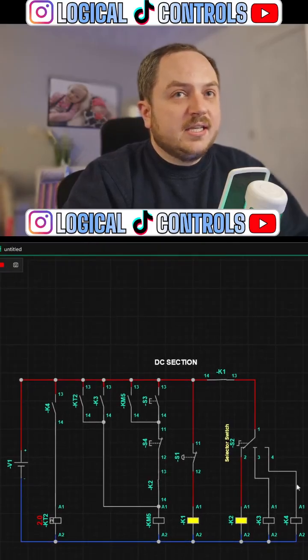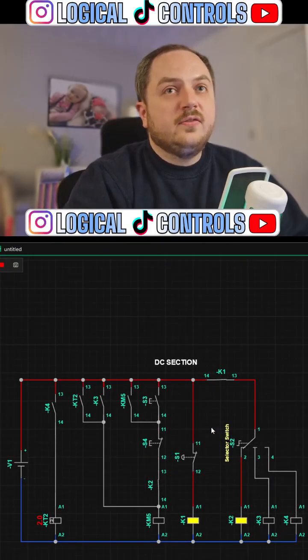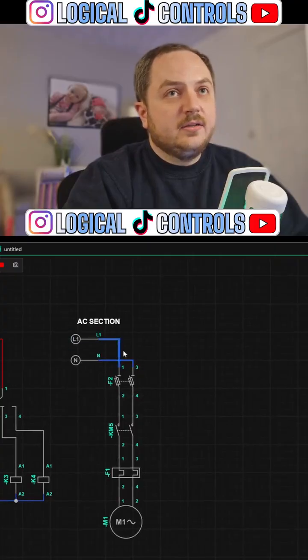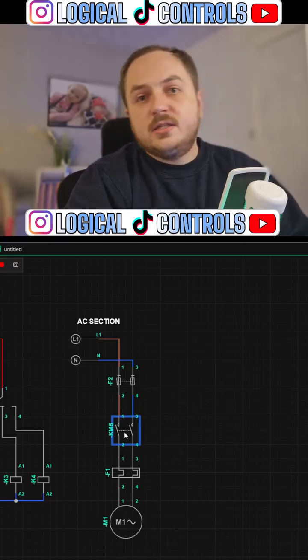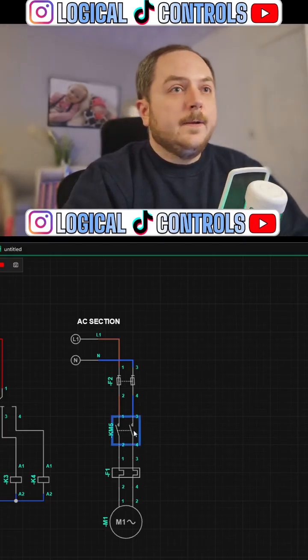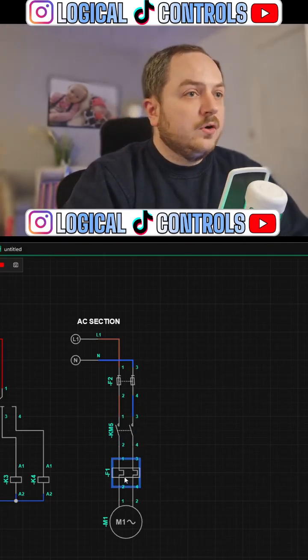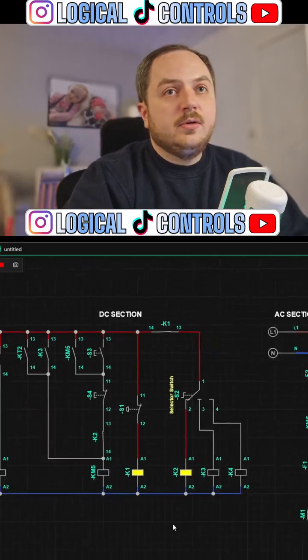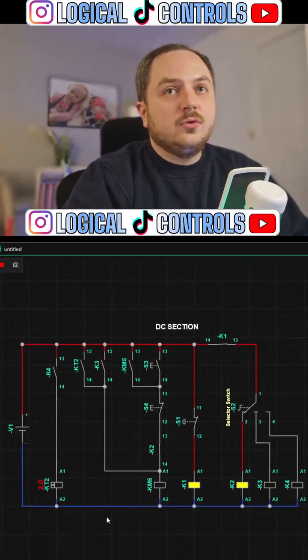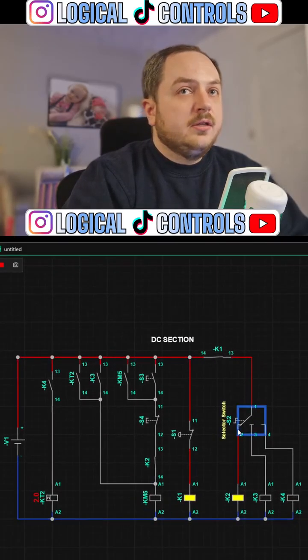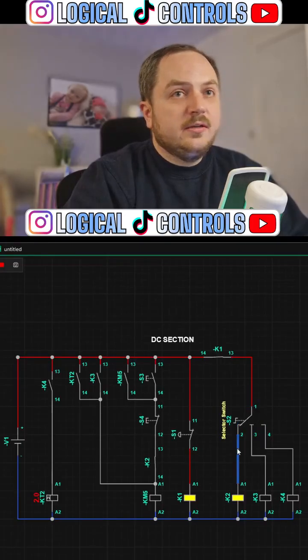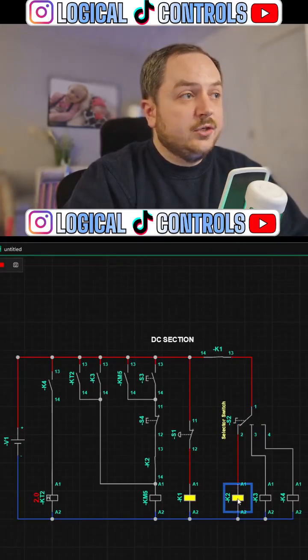We've got a DC side, so this is where all our controls live, and then we've got an AC side, just a single phase motor. Let's put the fuses on, the fuse switch, close it up. We've got a contactor there, that's normally open. We've got a thermal overload, which is closed. So for the control side of things, this position of the switch here, which is energizing K2, that's our manual position.